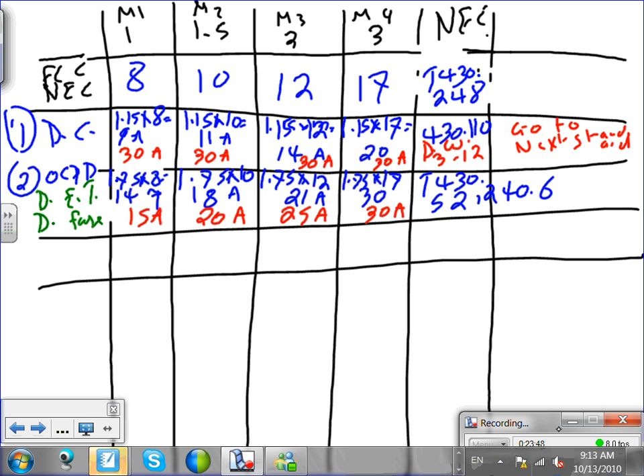So as we calculate the overcurrent protection device, if we don't hit a standard, if you read under this table, it tells you, don't worry. You have 2 options. Remember the 3 options? You go to the bar and cry and drink. Number 2, you custom design a fuse that's 14 amp, or the code allows you to go up. Going up doesn't mean you have to go up, guys. Can I go down if I know that the fuse works well with this motor?